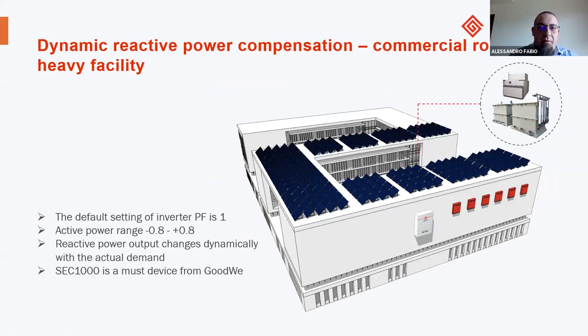Another function that we have in the terminal is reactive power compensation. If you need a special setting inside the inverter, you can set the cos phi and the reactive power output changes dynamically. You have the possibility to change it internally on the display. For each inverter, you can monitor and set up the cos phi inside the inverter.